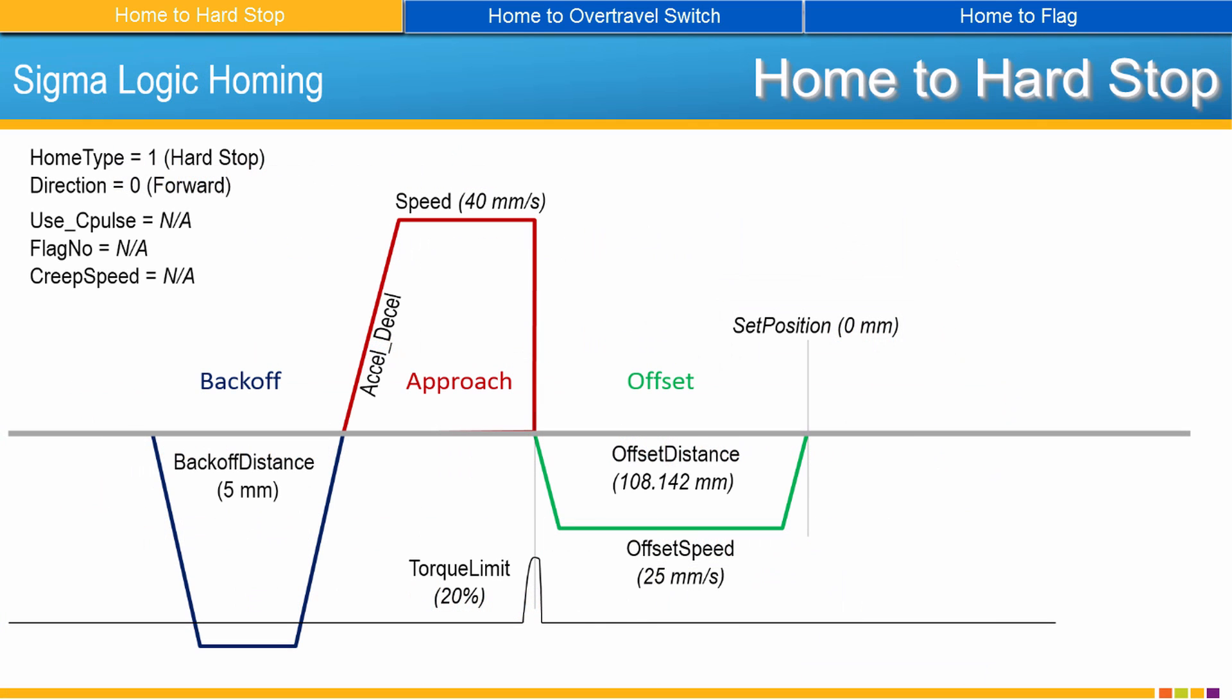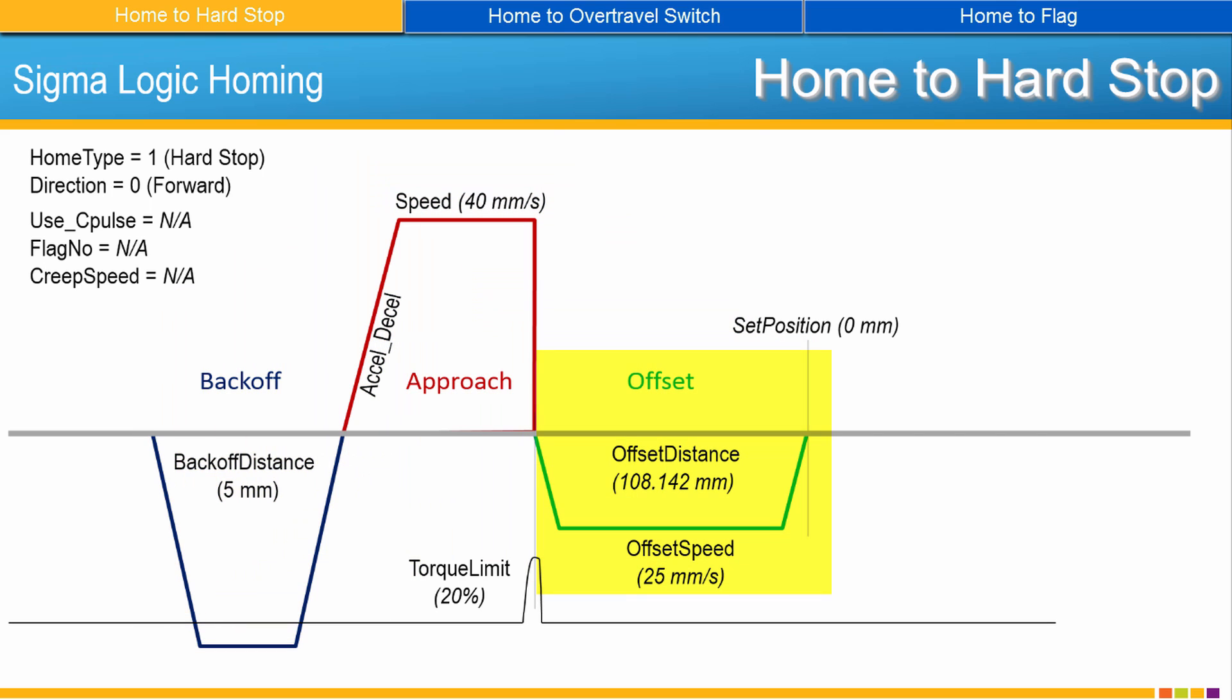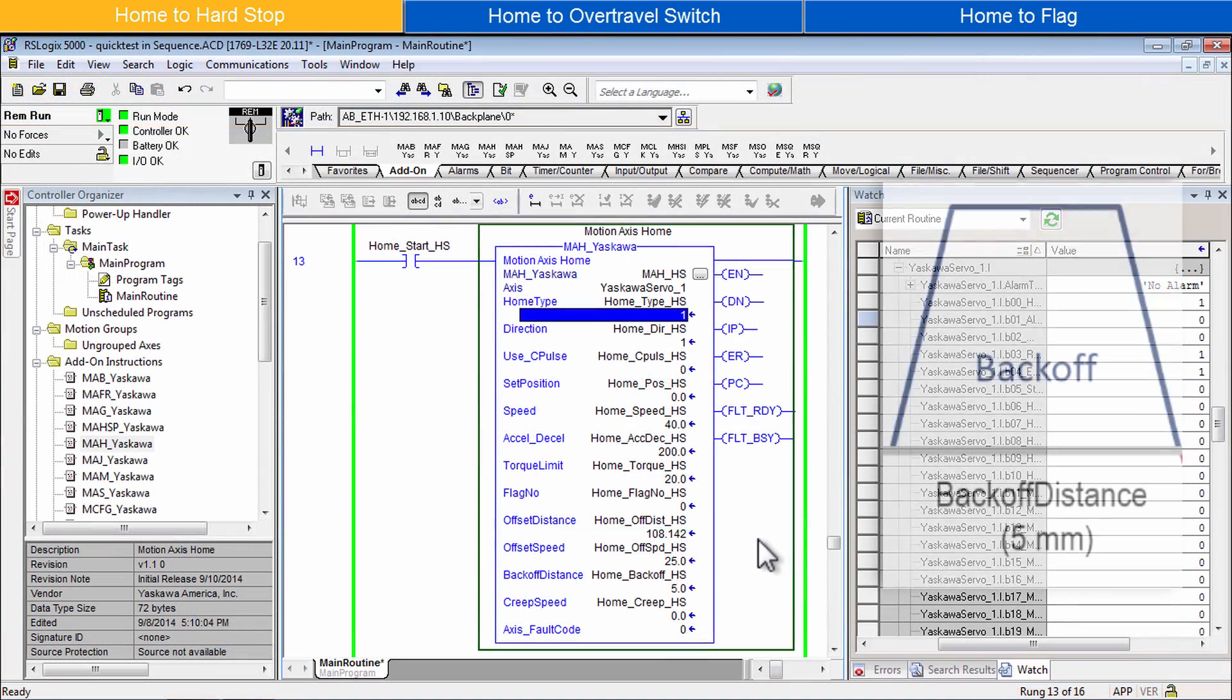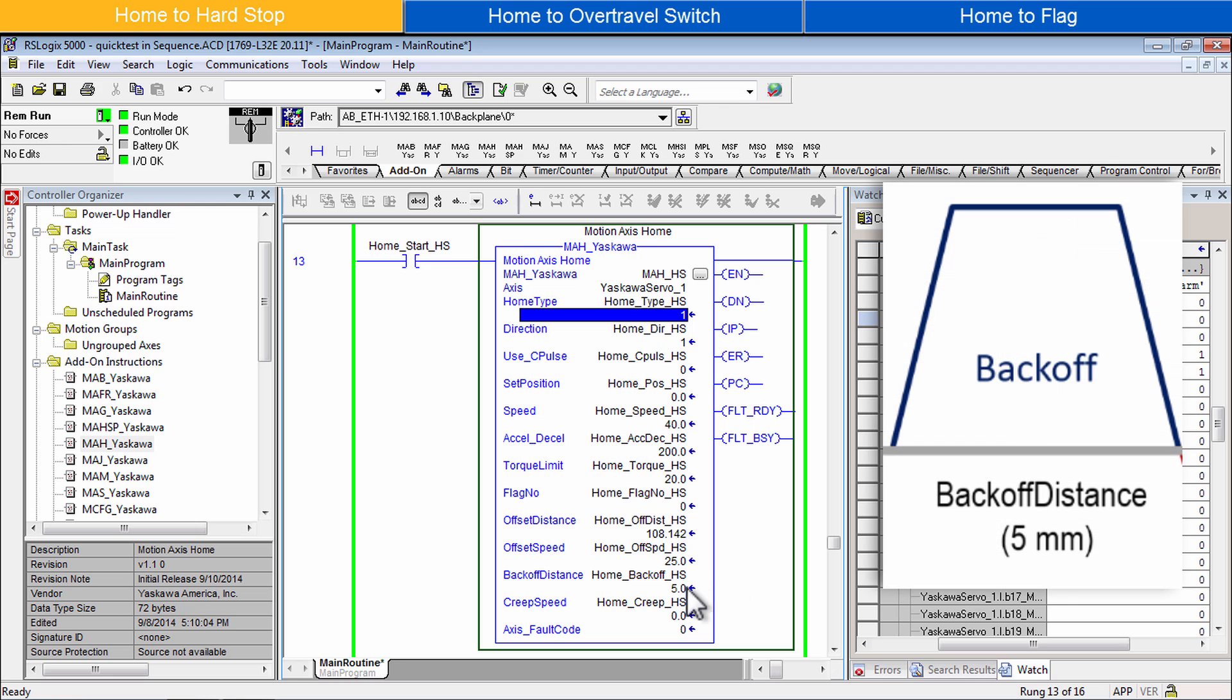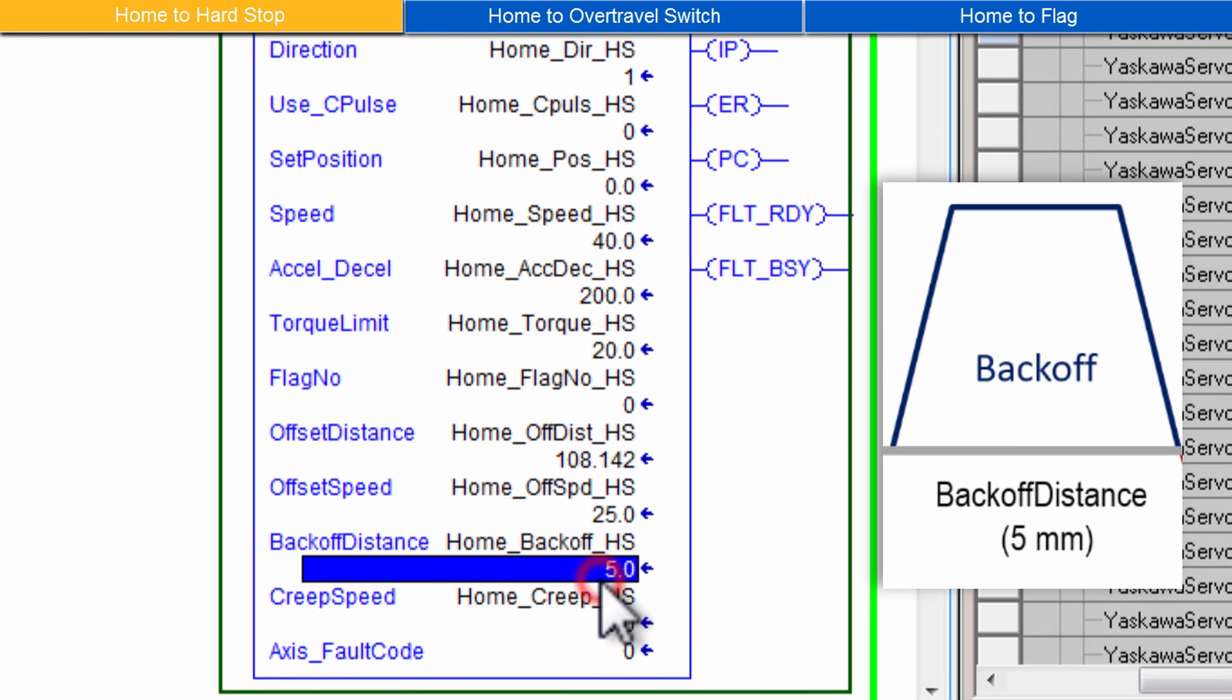Hard Stop Homing is a sequence of three moves: Back Off, Approach, and Offset. The AOI parameters will be discussed in the order of the move sequence. First set Back Off Distance to a small value. Keep it small in order to avoid the possibility of reversing into the opposite Hard Stop. I'll enter 5mm.